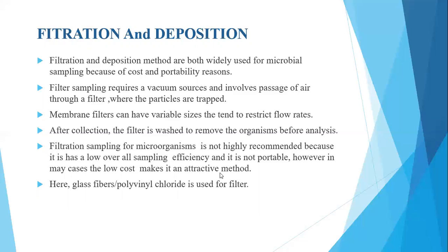Membrane filters can be of variable sizes that can tend to restrict the flow rate. After collection, the filter is washed to remove the organisms before the analysis. Filtration sampling for microorganisms is not highly recommended because it has a very low overall sampling efficiency. It is not portable. However, in many cases, low cost makes it an attractive method.